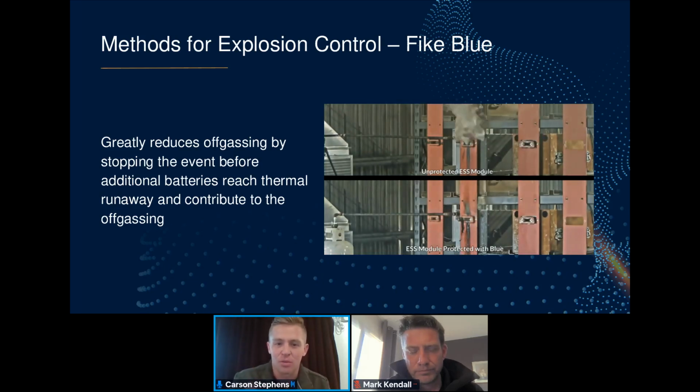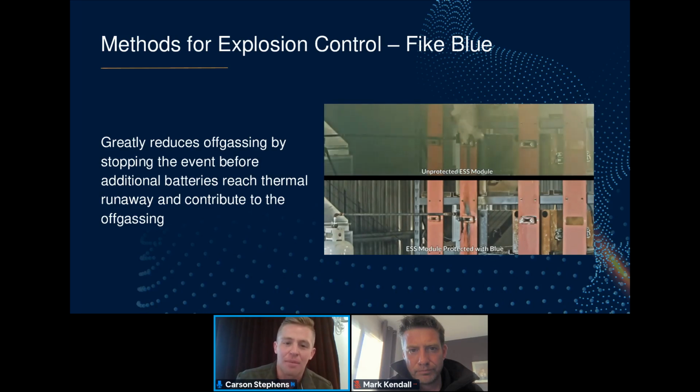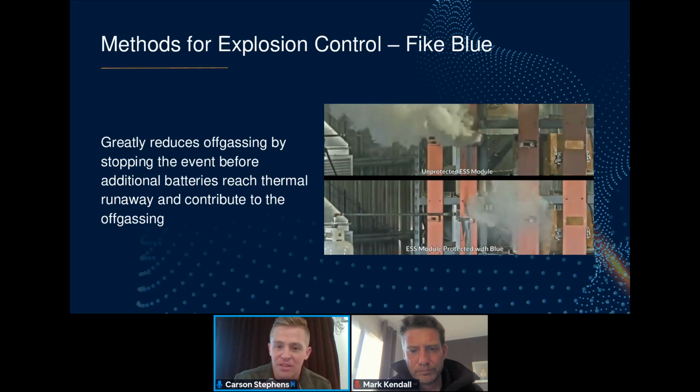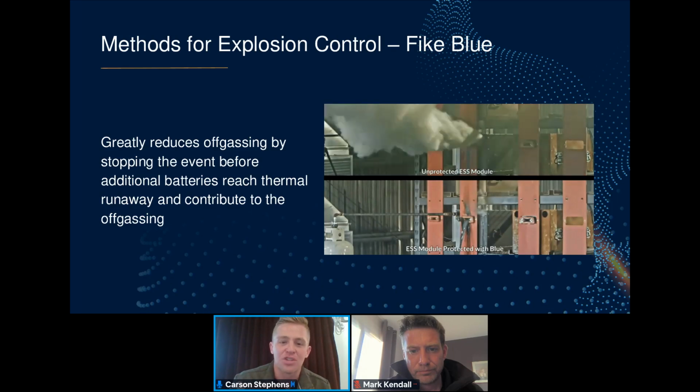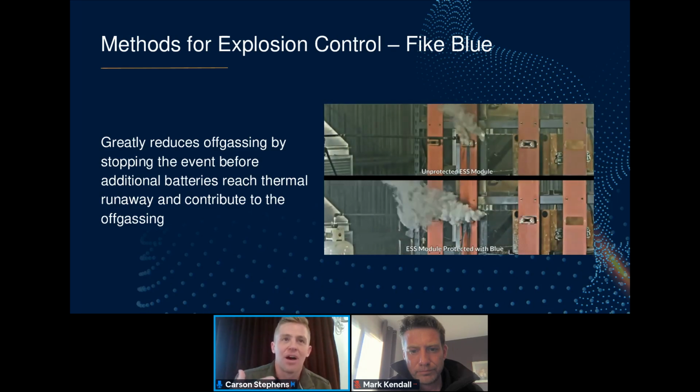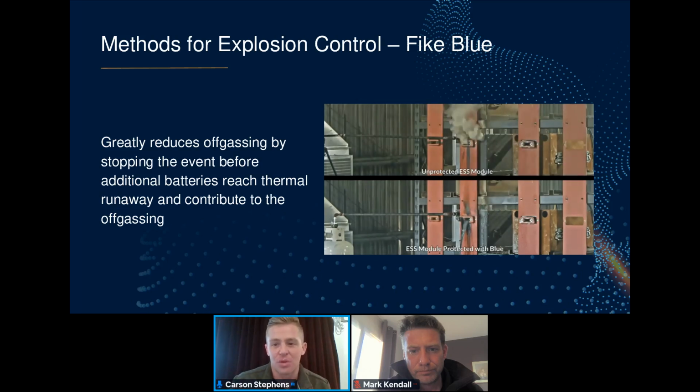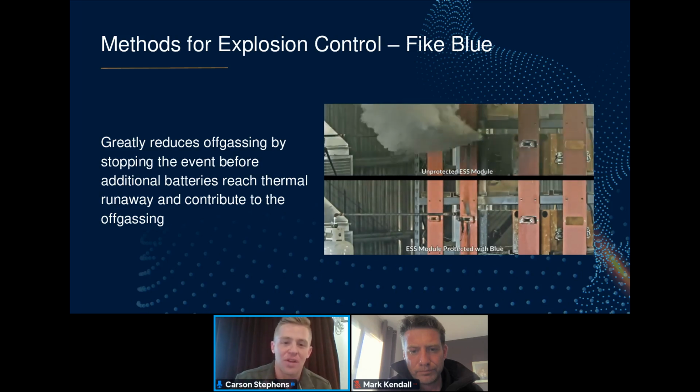So this is a really cool video that shows, in the bottom part, that when it goes into a thermal runaway event, now there's a little bit of smoke coming out, but that's residual heat coming off of the original cell that went into a thermal runaway event. If you don't take anything else out of this presentation, take this, because this is really cool.